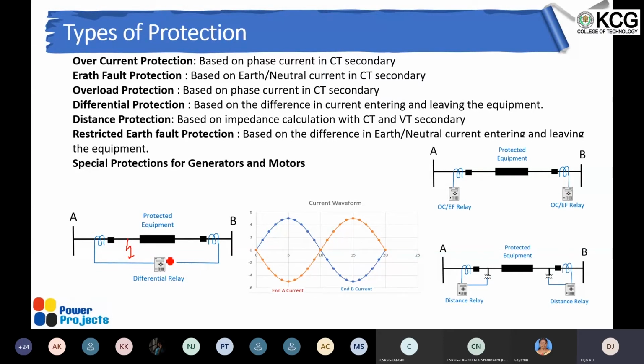Based on the current value, the tripping will happen. Let's assume the relay is set to operate at 1 amp in the secondary current, and for a fault, 2 amps or 3 amps comes. Then the relay operates and gives a trip signal to this circuit breaker. That's the simple principle of overcurrent protection, or the overcurrent relay.